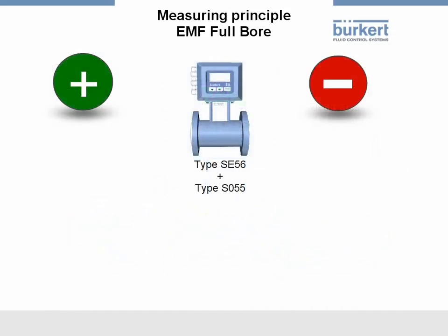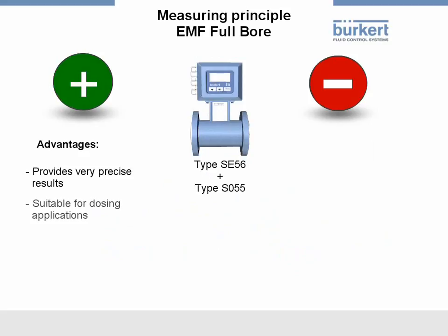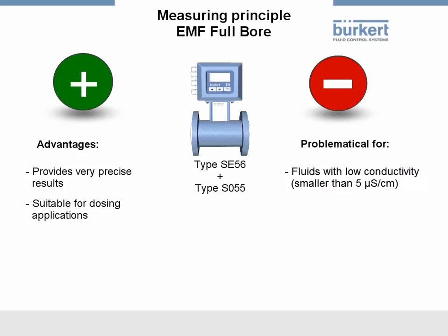The advantages of full-bore EMF are that this method provides very precise results and that it's suitable for dosing applications. Besides the general limits of application, such as temperatures and pressures, the applications of this measuring method are restricted only by fluids with low conductivity, smaller than 5 microsiemens per centimeter, ferromagnetic particles in the medium, coat-forming fluids, and fluids with a highly abrasive effect.